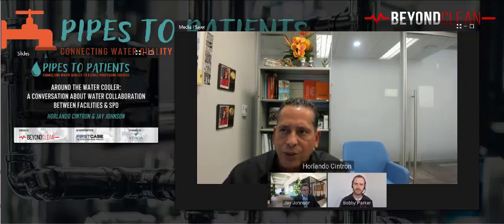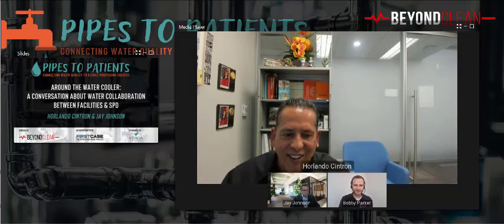Apart from instrument staining, what I've also run across recently was staining in my washer. The amount of white residue that was coming through in our system, in our washer, was really a trouble. There was a lot of tug of war and finger pointing between the RO system and the manufacturer. And believe it or not, in that particular instance, it turned out to be an issue with the chemical we were using in our washers to clean. By changing that out, we were able to address the issue and bring it to an end. It wasn't the washer, wasn't the actual RO system, but the chemicals we were using to clean in the washer that was the cause. So it's a hard task, I've got to say.